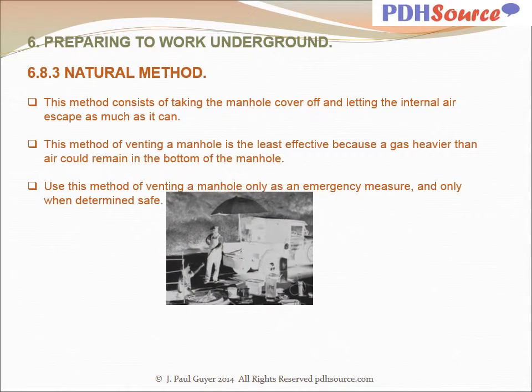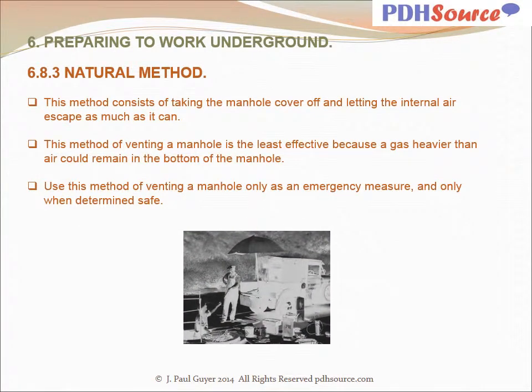The natural method consists of taking the manhole cover off and letting the internal air escape as much as it can. This method of venting a manhole is the least effective because a gas heavier than air could remain in the bottom of the manhole. Use this method of venting a manhole only as an emergency measure and only when determined safe.